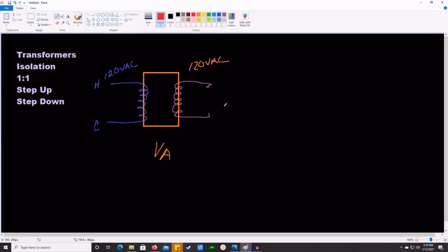Actually, on either side, it's really a fire waiting to happen. So that's what we're going to do: check to make sure we have continuity across this coil, that there's no breaks in that wire. We're going to look for continuity across the coil to confirm there's no breaks, and then make sure we do not have continuity between this wire and the transformer, this wire and the transformer, and these two wires, all independently. We want everything electrically isolated. That's essentially how we test for function in a transformer. It won't tell you anything about the values - there's a whole other test for that, a different video. We're just talking about the basic function of the transformer.